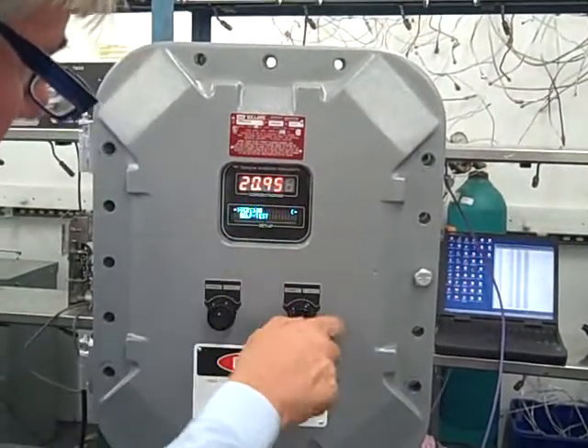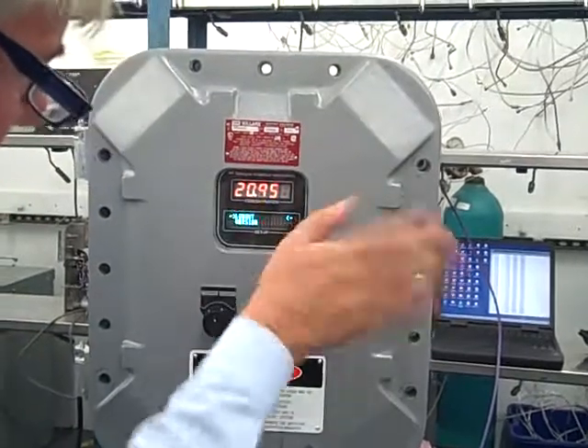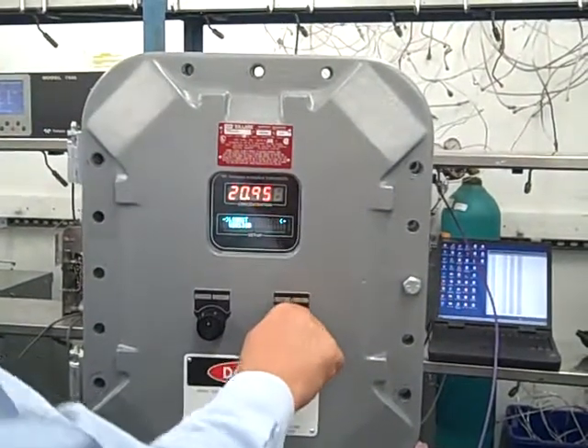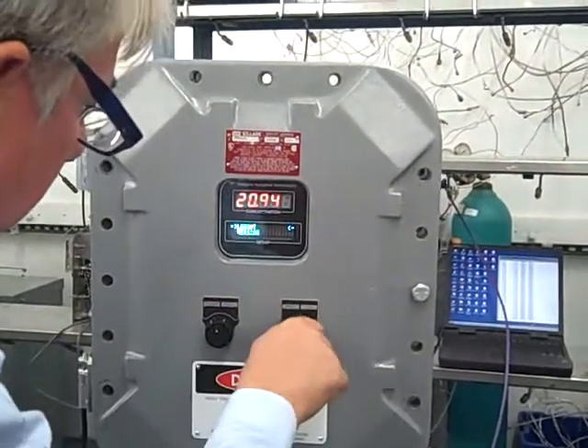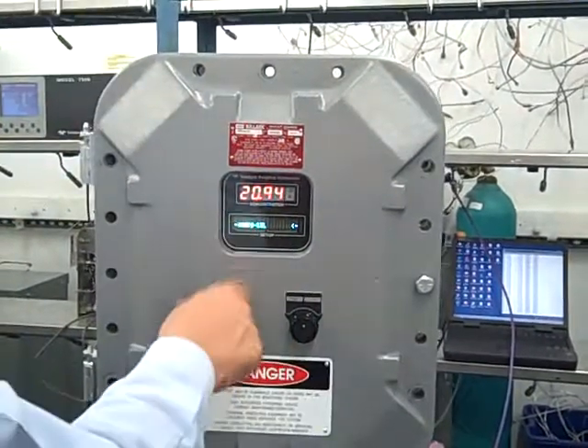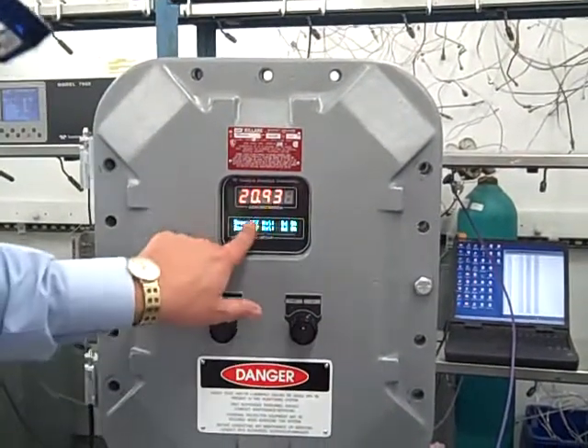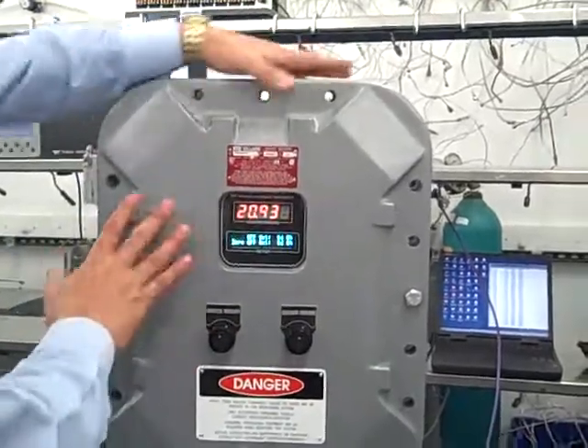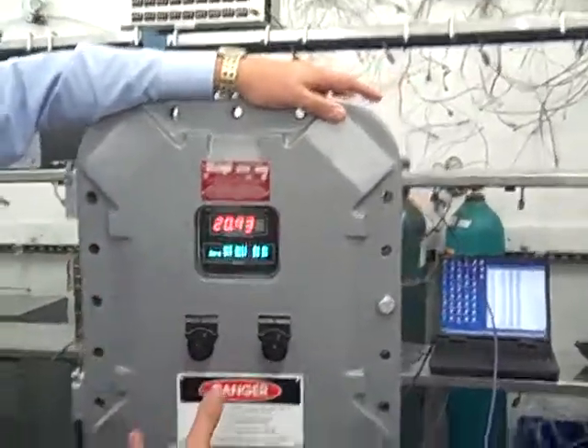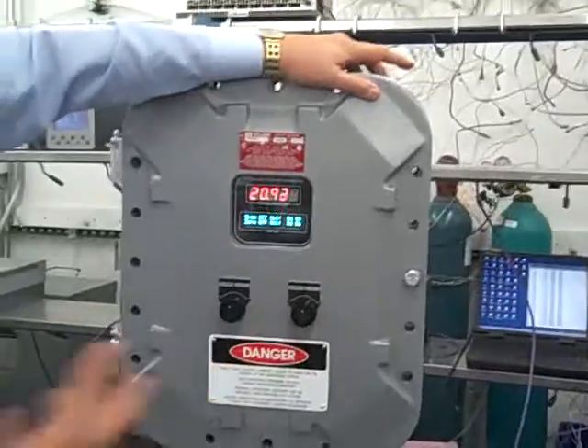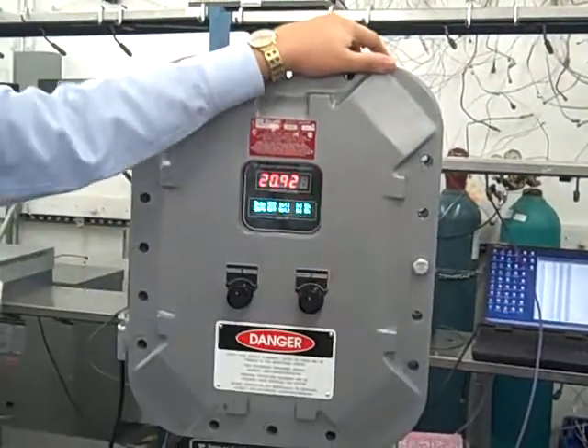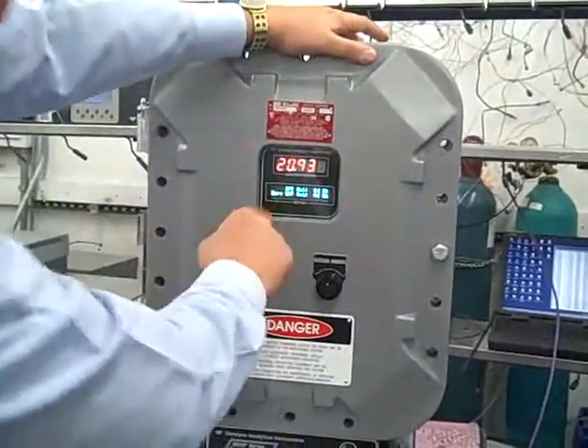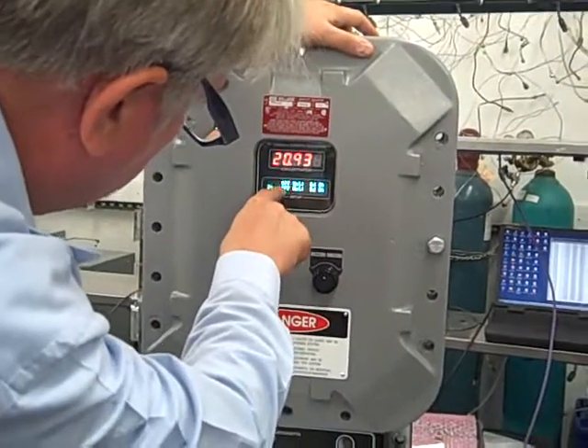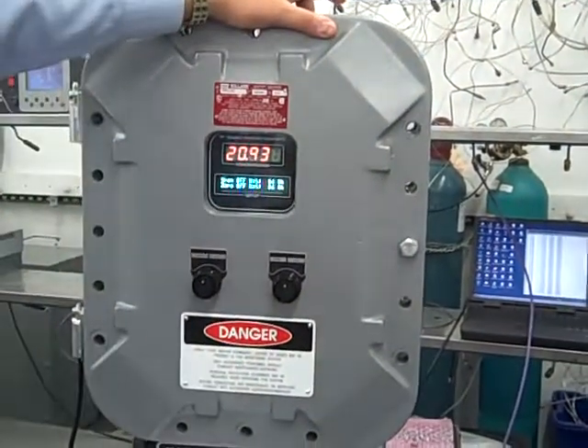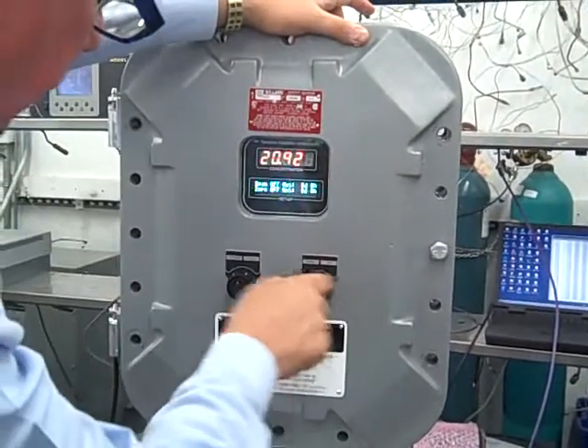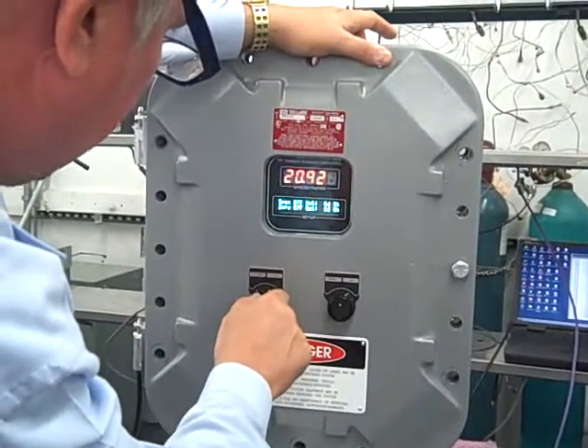Version. This tells you the software version. We already went through self-test. Log out is something you don't want to worry about. AutoCal, this is of interest to some people that want to set up auto calibration intervals. This equipment is available with auto calibration valves, so you can connect span gas and zero gas. And again, we don't recommend using zero gas most of the time, but so you can schedule, notice here, right now it says span off. That means there's no automatic span enabled, but you can go ahead and change that.